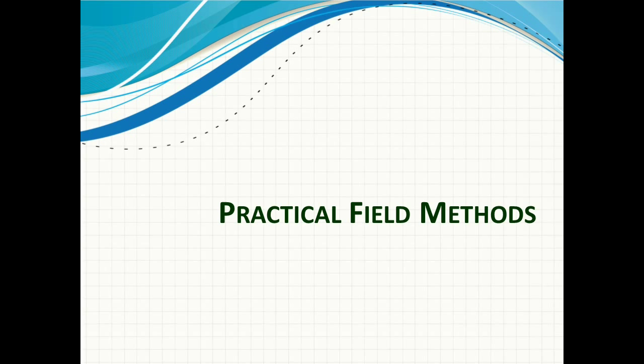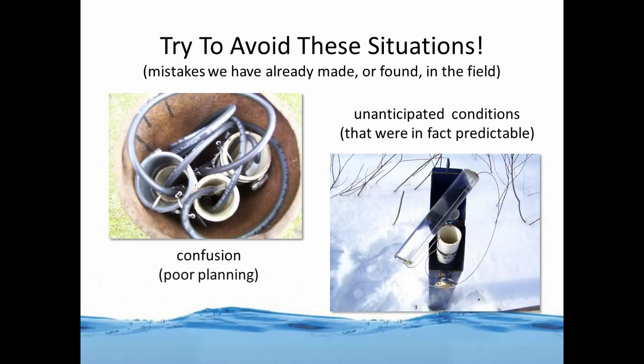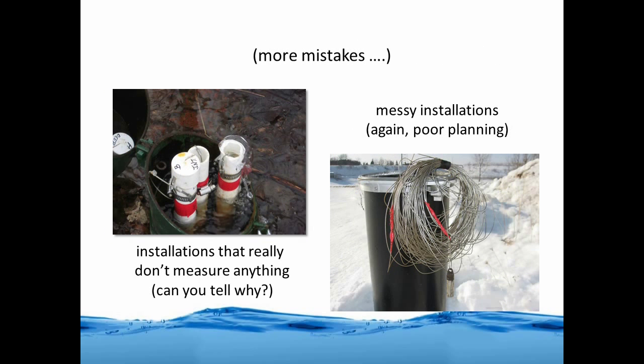This brings us to the last section: practical field methods. In the photos on this slide, we want to avoid these situations — mistakes found in the field or that we've made ourselves, some resulting from poor planning. There are also installations measuring practically nothing at all, such as a flowing well on the left, as well as messy installations where poor planning has resulted in a mess of cable and data logger readings that are not going to be reliable.